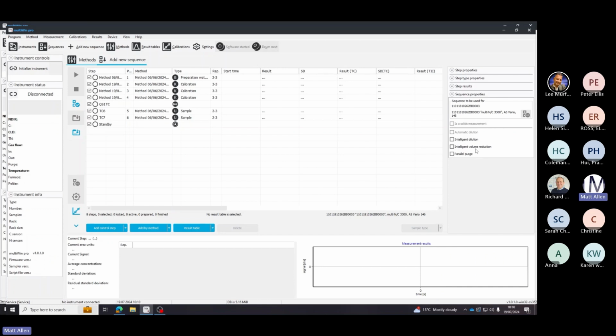So if you're doing a 0 to 100 calibration curve, but you're not sure what your sample concentration is going to be, you might have 500 ppm, for example, then it will run the first sample, see it's outside the range, and then it will reduce the volume and bring it back into the range, and the sample will then be marked up as using the intelligent volume reduction. So just below that you can see parallel purge, and this is if we're doing NPOC. So we would be adding the acid into the vial, and while we are purging the inorganics out of that vial, we will actually begin to sample the previous vial. So it's actually just saving time. One vial will be getting purged of the inorganics, while the previous one will actually be getting measured.